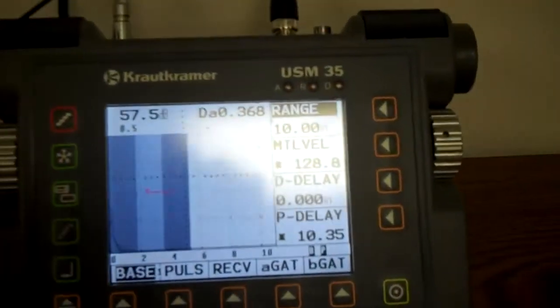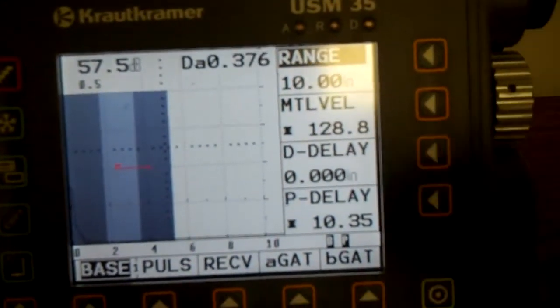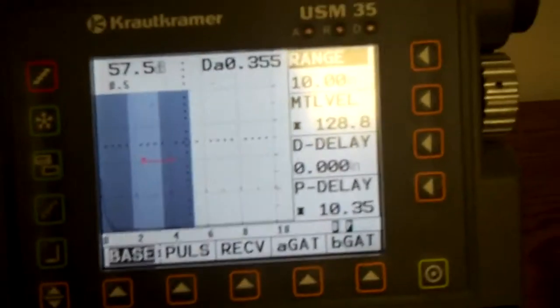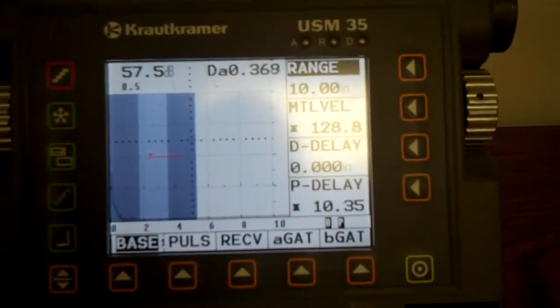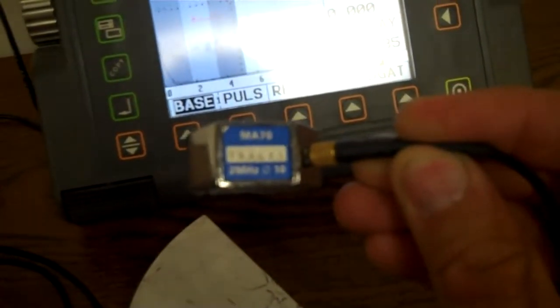Good afternoon. Been a while since I've generated a video. I wanted to generate a video over shear wave inspection, or at least calibration of shear wave inspection, using currently the mini angle beam block, and I have connected a 70-degree transducer. Get that maybe in focus so you can see it a little bit better. That's 2 megahertz.